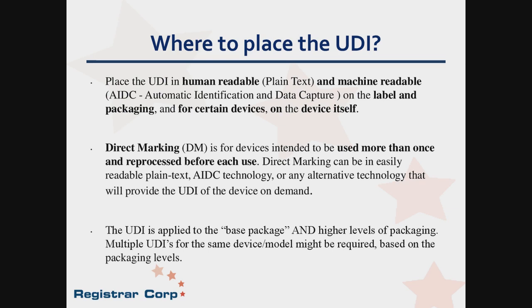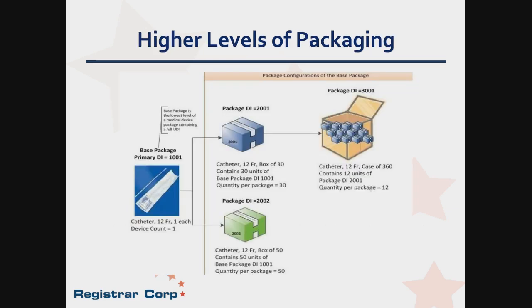Also, the FDA regulation requires a UDI for higher packaging. So it's not only that you have a UDI on the base package, everything that you also have as an order number in higher packaging numbers, we will see that on the next slide here, would require a UDI. So for example, you have a catheter here, which is the base package, and you create a UDI for that. Since one catheter is not very much, and if you think of a hospital, they are using them constantly, you have packages in that example. There's a package of 30 in one big box. This is a box that has your label and that someone can order. So that is called higher packaging, and that blue box would also require its own UDI.